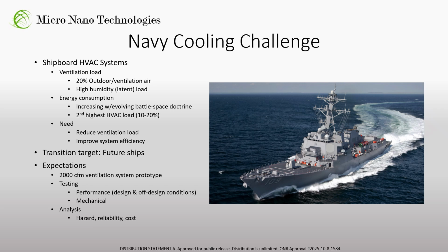HVAC systems are critical to the effective operation of modern naval vessels, ensuring the health and comfort of the crew and the functionality of the ship's combat and control systems. Naval ships, similar to commercial buildings, are required to provide 20% of outdoor replenishment or ventilation air. Given the high humidity loads typical of maritime climates, shipboard HVAC systems consume a significant amount of energy dehumidifying this ventilation air, typically 10 to 20% of the total cooling load during summer. This represents the second highest cooling load within the ship. This is due to the operating principle of current HVAC systems that need to subcool the air to remove moisture by condensation on cooling coils.